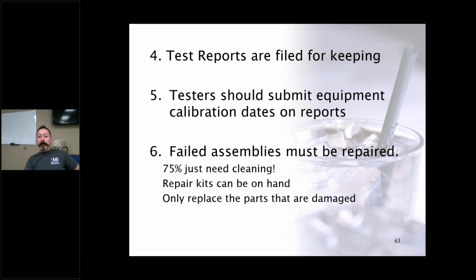Okay. Failed assemblies must be repaired. That's another thing you'll get: the tester will come out and fail the backflow preventer because it's not functioning correctly, and then leave it. Or the next year they'll test it again and it still failed. So what has to happen is that once these things fail, they need to be repaired. And half the time, 75% of the time, they just need cleaning.